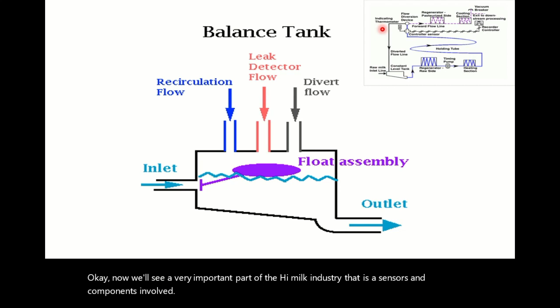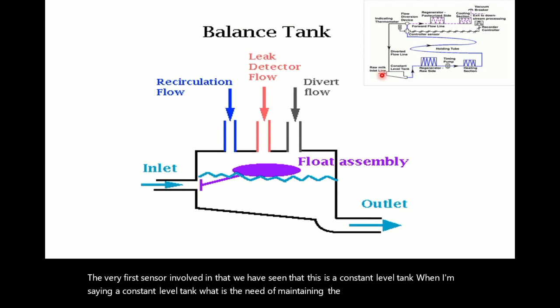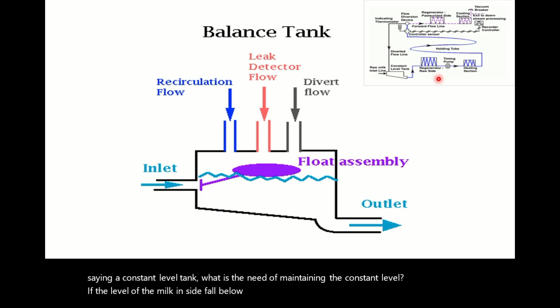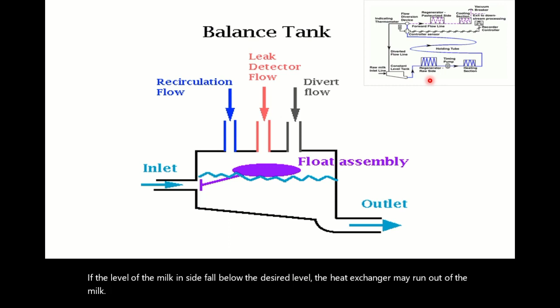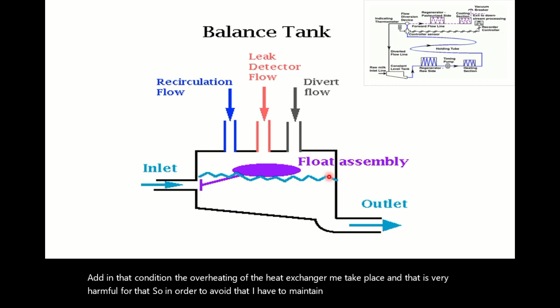The very first sensor involved is in the constant level tank. What is the need of maintaining a constant level? If the level of the milk inside falls below the desired level, the heat exchanger may run out of milk, and in that condition overheating of the heat exchanger may take place, and that is very harmful. So in order to avoid that, I have to maintain a constant level throughout. This is done with the help of a simple float assembly.